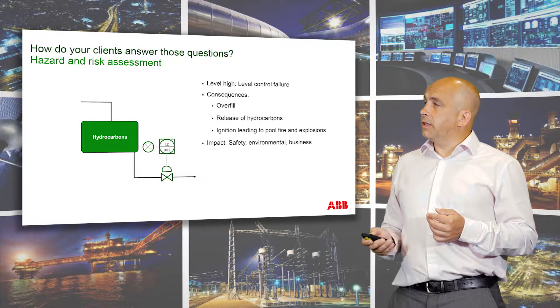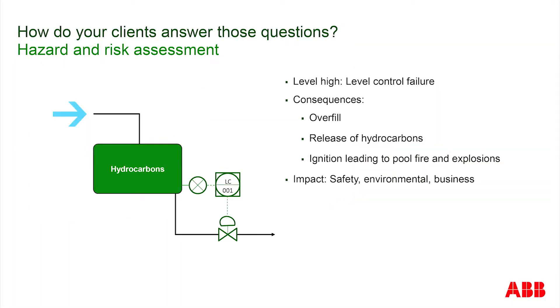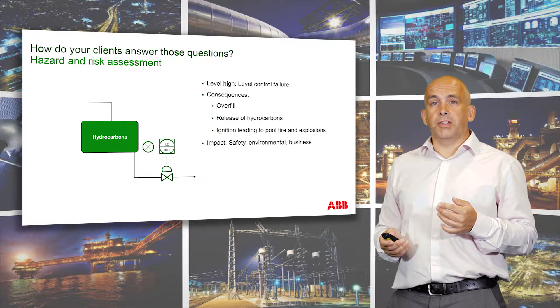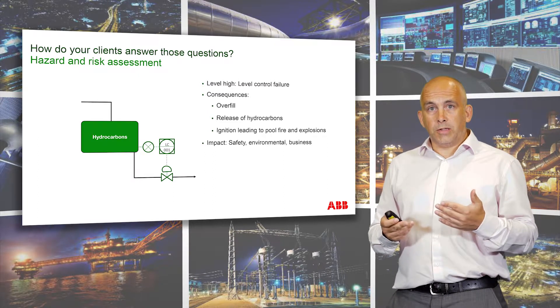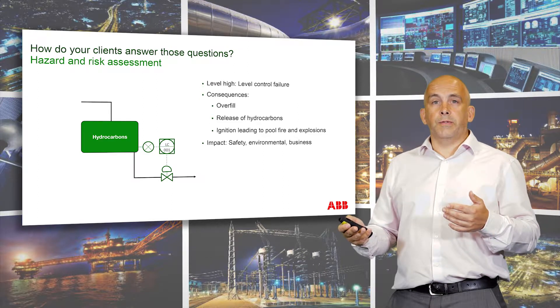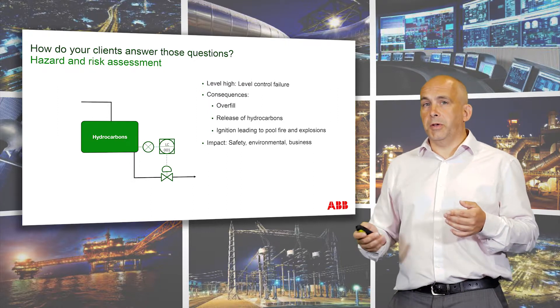To explain this, I'm going to use this simple example of a separator. We have flow coming in and flow going out. To control the level in that separator, we've got a level controller. So what can go wrong? Well, if we have a problem with that level controller, the level may rise. If it rises too high, we may overflow that particular vessel. If we overflow the vessel, then the hydrocarbons could flow and find a source of ignition. If it finds a source of ignition, then we could have a fire, maybe an explosion.